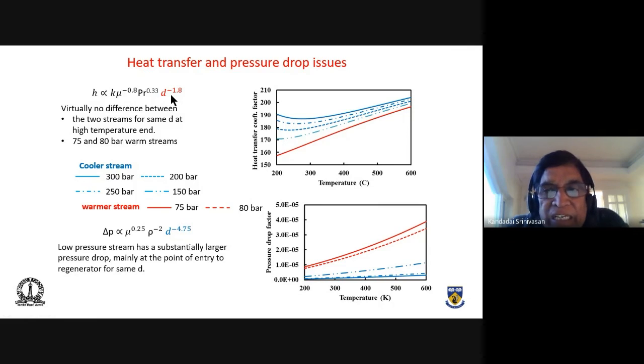So in a turbulent region, and we would like to always be in the turbulent region, the heat transfer coefficient is proportional to velocity power 0.8. In the laminar region, it is velocity power 0.5. So that's why we want to be in the turbulent region, number one. Number two, when it comes to the question of pressure drop, whether it's laminar or turbulent, it's immaterial. The pressure drop is proportional to velocity power 2. When you increase the velocity, your heat transfer coefficient doesn't rise proportionately, it only rises by a power of 0.8. But when you increase the velocity, the pressure drop goes as the square. So this is something you have to be aware of. Always increasing the velocity is not a good idea, because you are going to increase the pressure drop too.